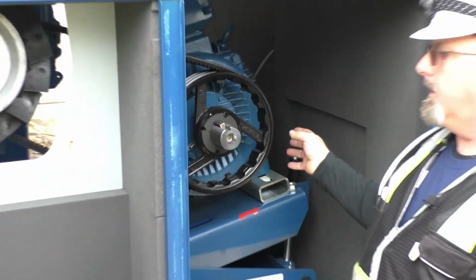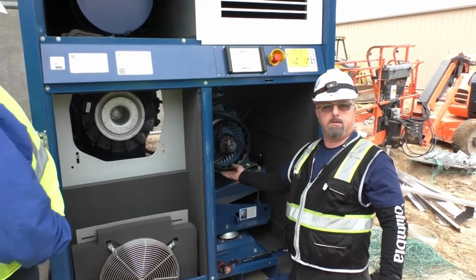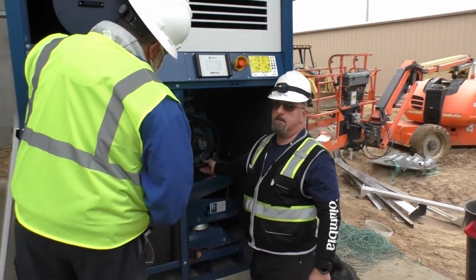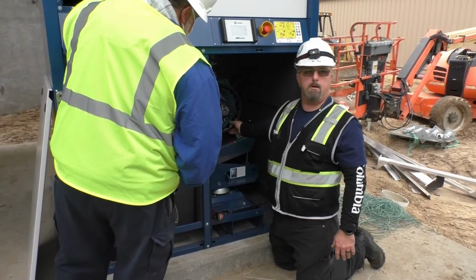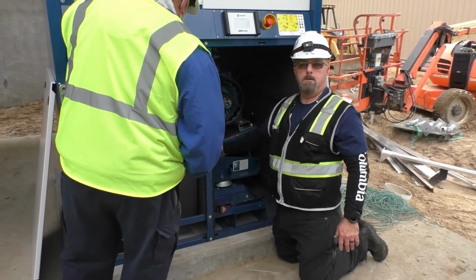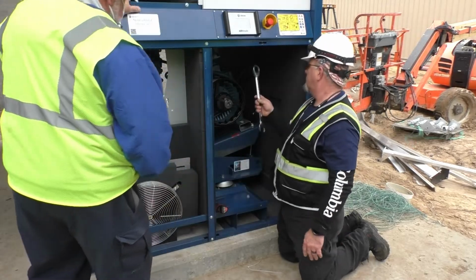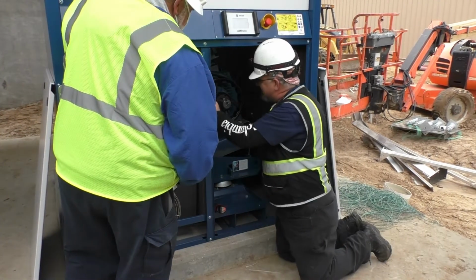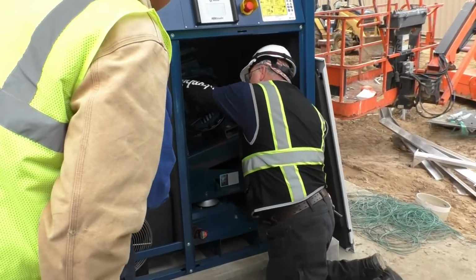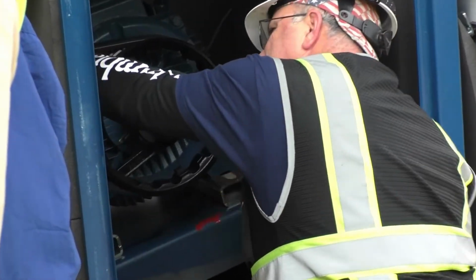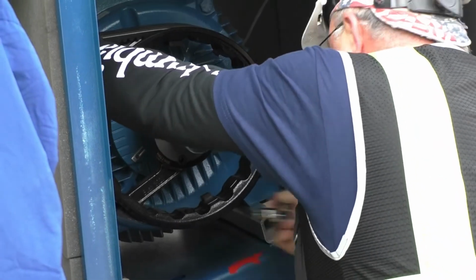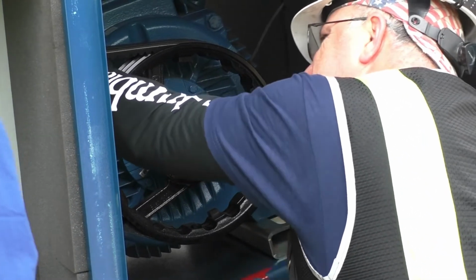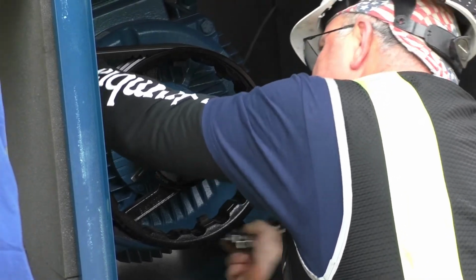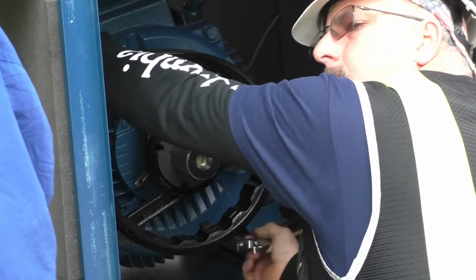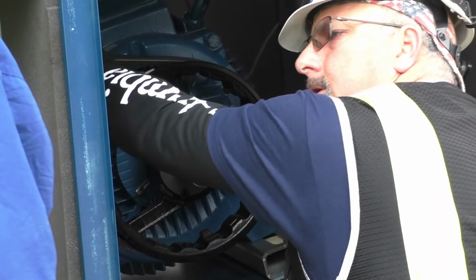Now, the one thing I can't stress enough, when you roll the belts off and on, you notice I had just a bare slight bit of tension on the first belt. Do not let the belts take all the motor weight rolling them on and off. That will damage the cords in the belt. Once you do that, you take your wrench. I usually hold my hand on the belts so that way they stay in the grooves.